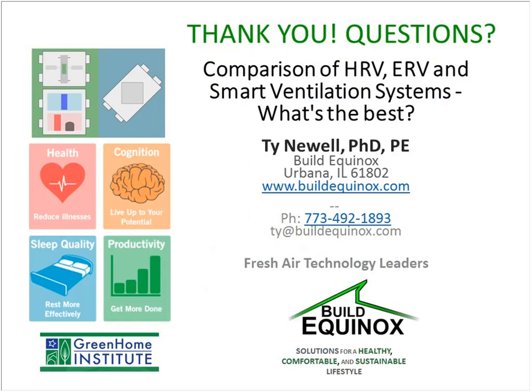And as you saw in that Vermont data that I showed, those homes all have our smart ventilation system in them, and you saw them operating in temperatures down to -10, -20. We've collected data from one home where it got down to -26 Fahrenheit. And so we absolutely know that we're able to manage frost without sacrificing fresh air ventilation in as harsh a winter as you might find in the U.S.